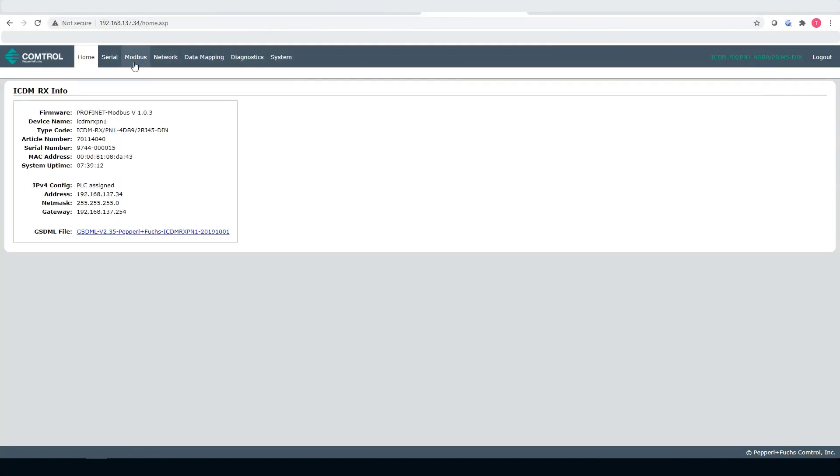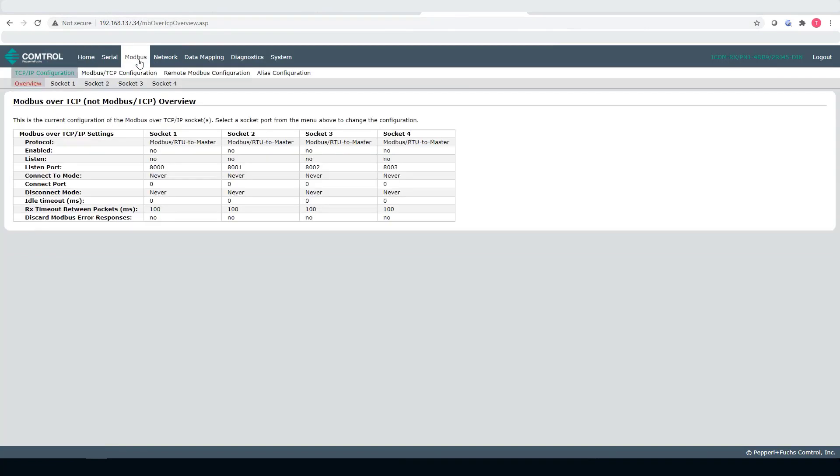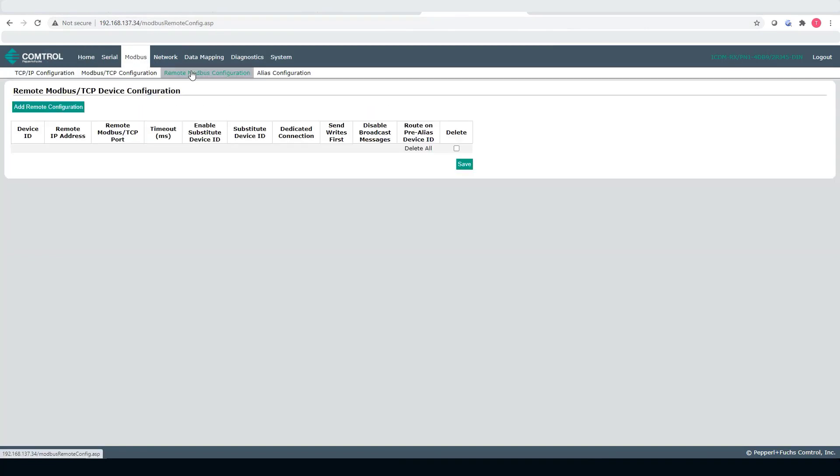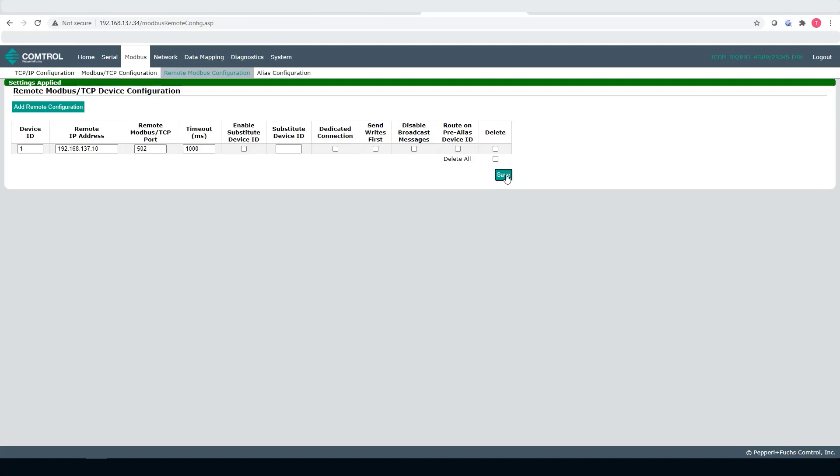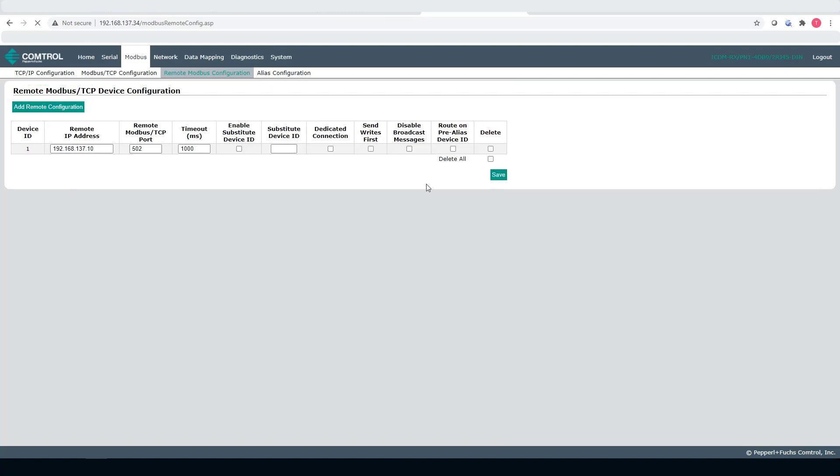Now that I've configured my IP address, I enter that IP address directly in my web browser. And then I want to go to the Modbus, remote Modbus configuration and I want to add my Modbus device here. So, device ID 1, 192.168.137.10, leave everything else default and choose save.